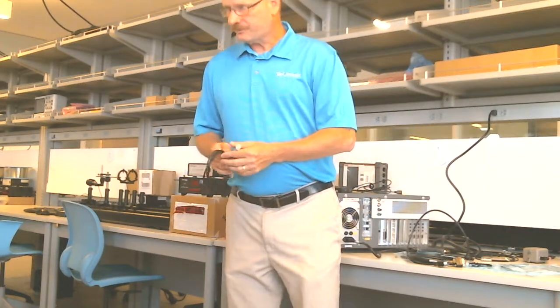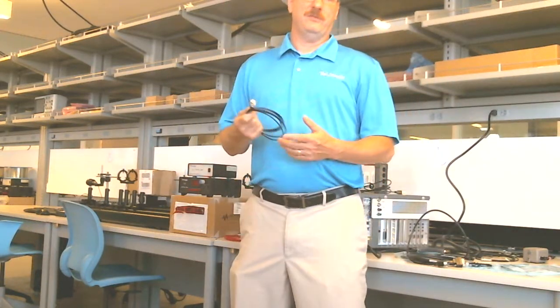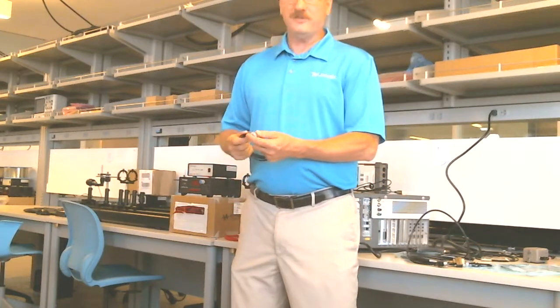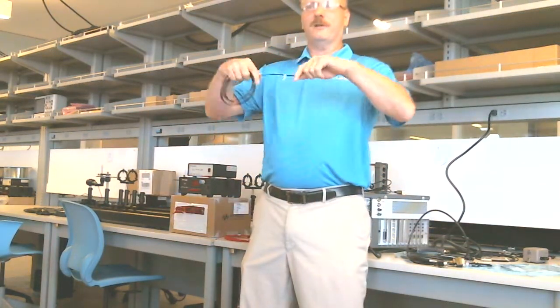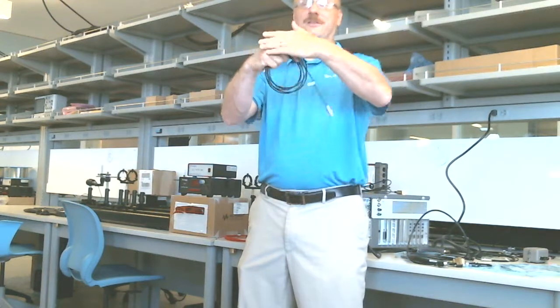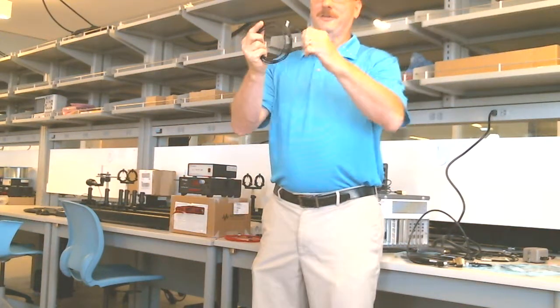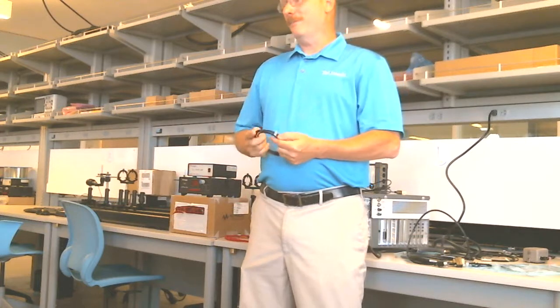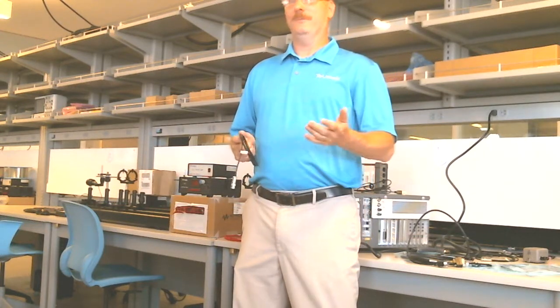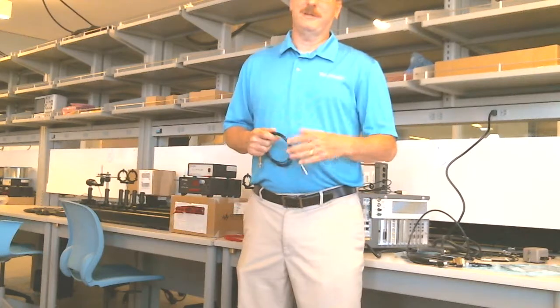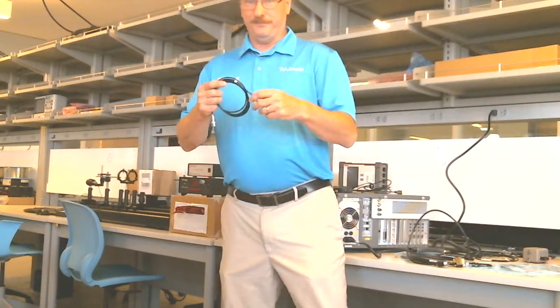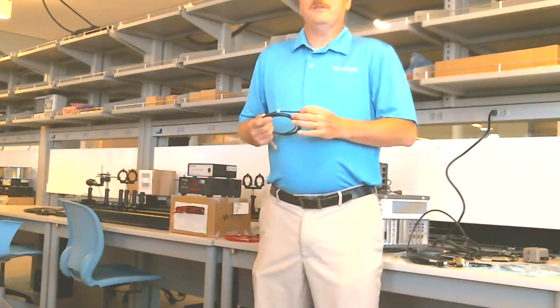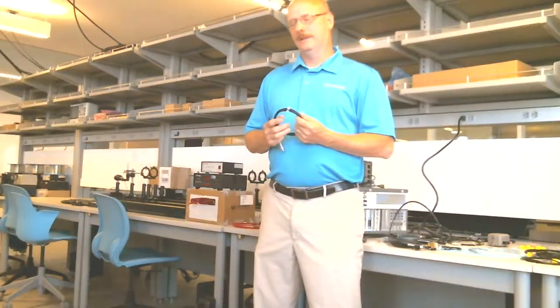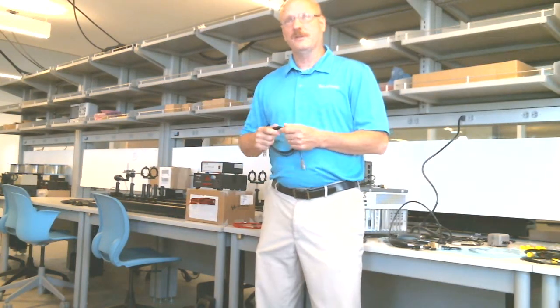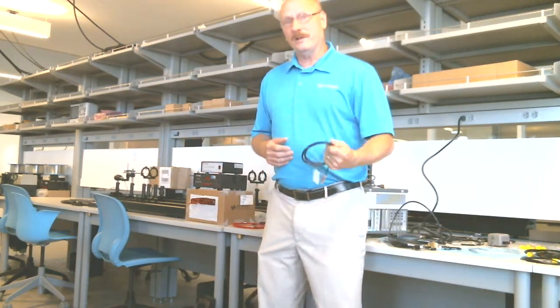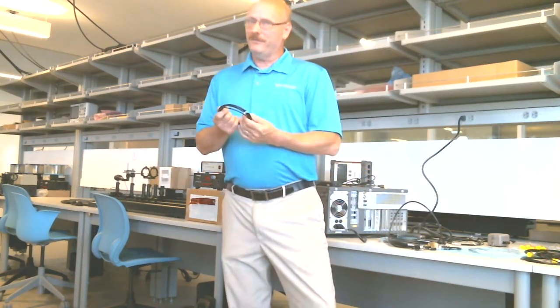This cable has leakage, all cables have leakage, right? It also has capacitance, and it also has triboelectric effects - when you rub the insulator against the conductor, you generate voltages. All those things matter now when you're in the femtoamp range, they're going to be significant. But these cables are low noise, so they have very low triboelectric effects. They're very good quality cables, low inductance and low capacitance, but they still have leakage.